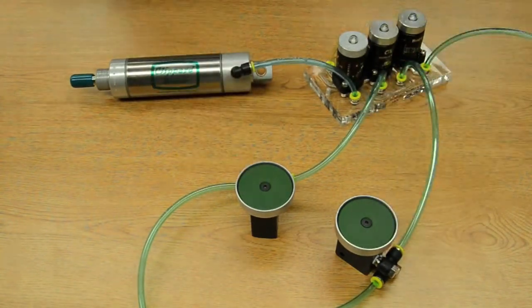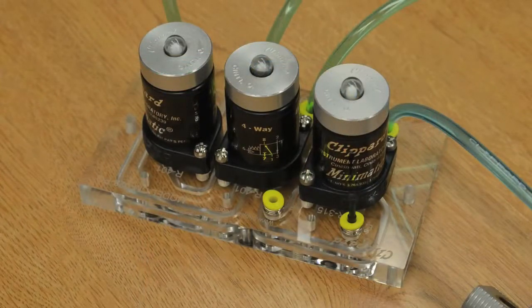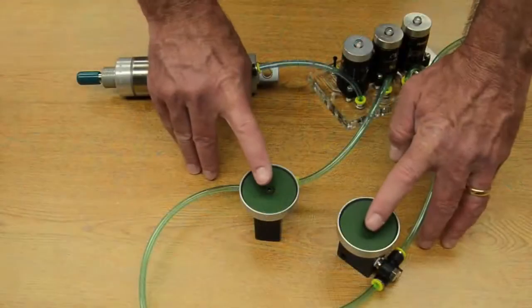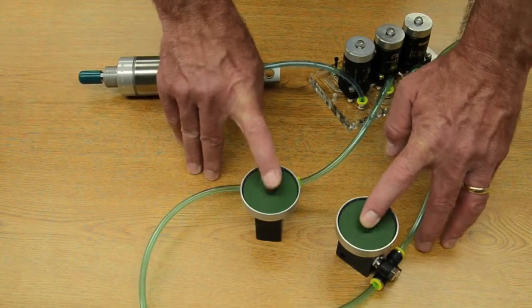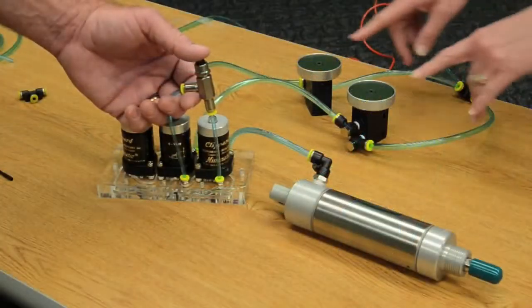The next feature is a cancelable output and what will occur is when you push both buttons, you'll get an output for approximately 50 milliseconds and then the output will exhaust. This is a cancelable output feature.